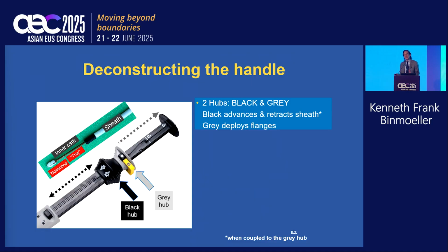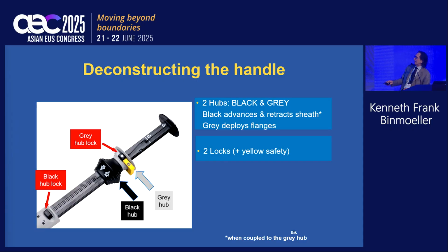So what I'd like to do now is take a look with you under the hood. It's important that you understand how that handle works. That's going to be very important when you need to troubleshoot. So we have two hubs, a black hub here and a gray hub here. The black hub advances and retracts the sheath, but it only does that when the two are coupled. That is key. The black and the gray hub must be coupled. There are two locks, a black hub lock here, and a gray hub lock here, and there is a yellow safety pin. This keeps the black and the gray hubs coupled until you are ready to uncouple the two.